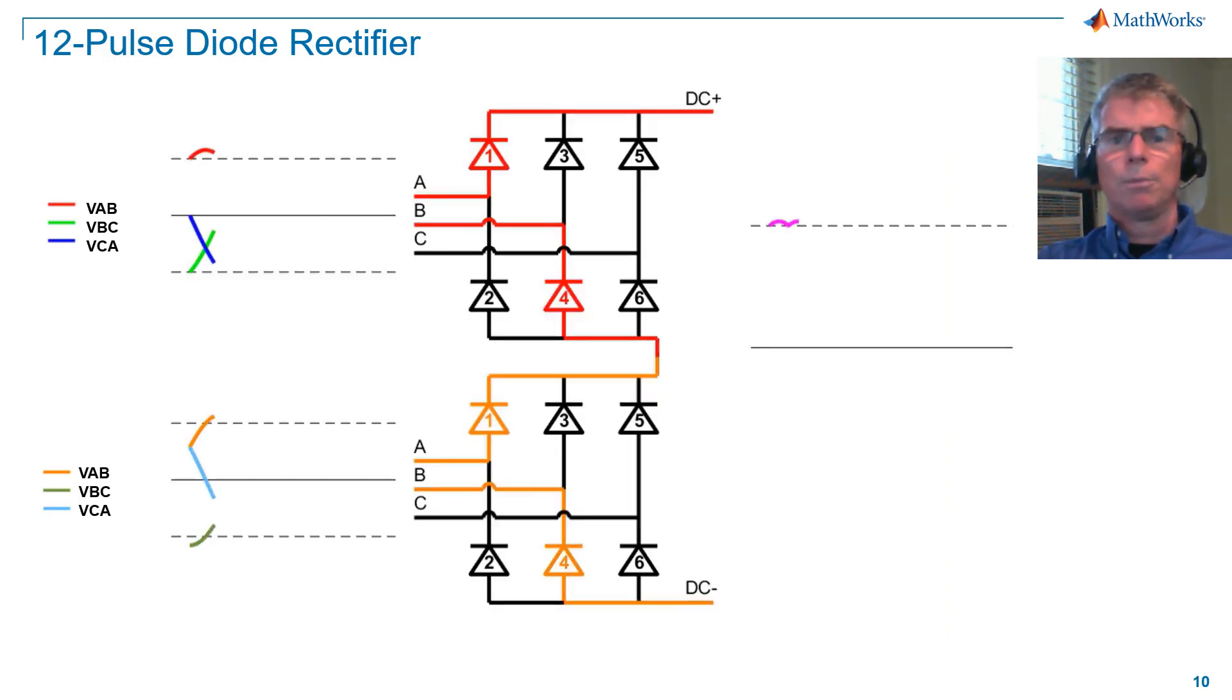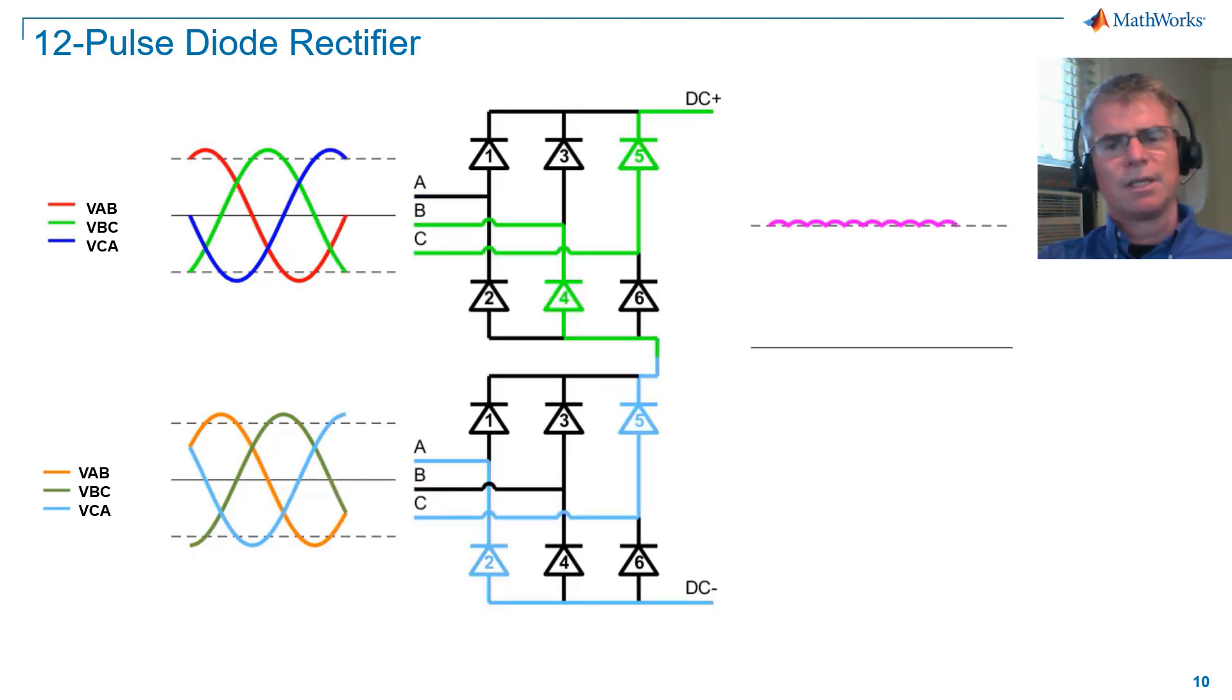Now you can see that we are commutating at 30-degree intervals, and as a consequence, we've lowered the DC voltage ripple. We've now achieved true 12-pulse operation with our 12 devices. Note that we can extend these architectures to 18-pulse, 24-pulse, and so on, but we won't cover that in this tutorial.